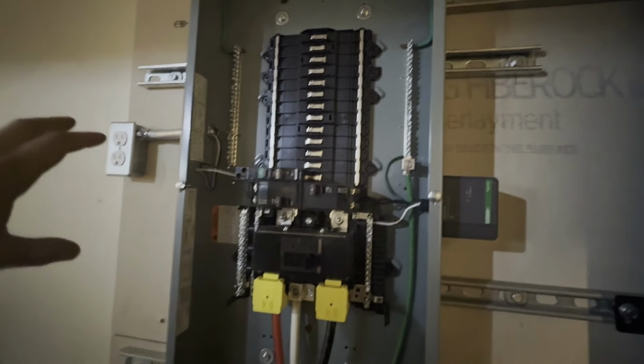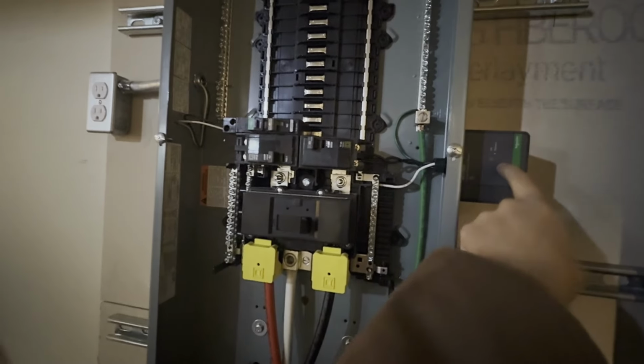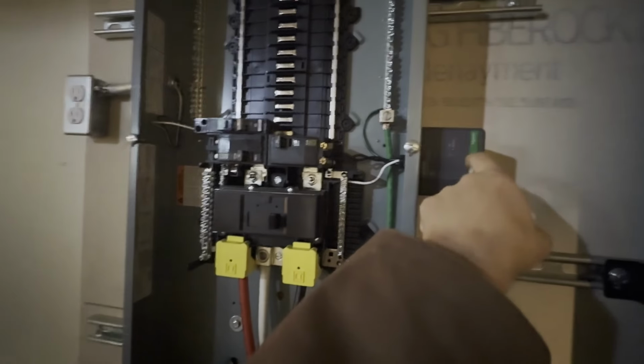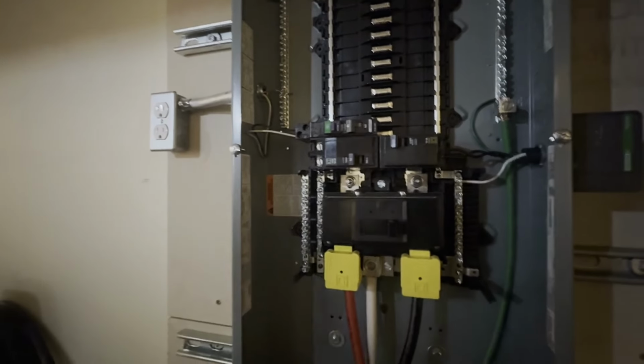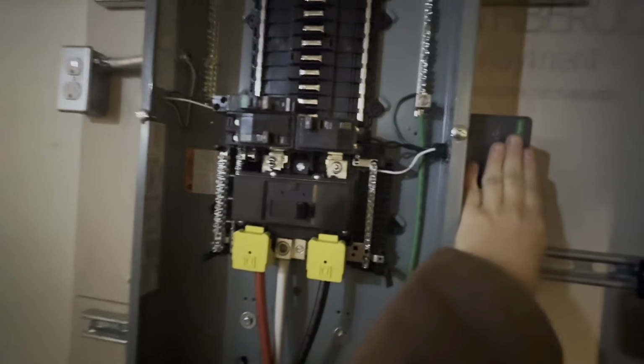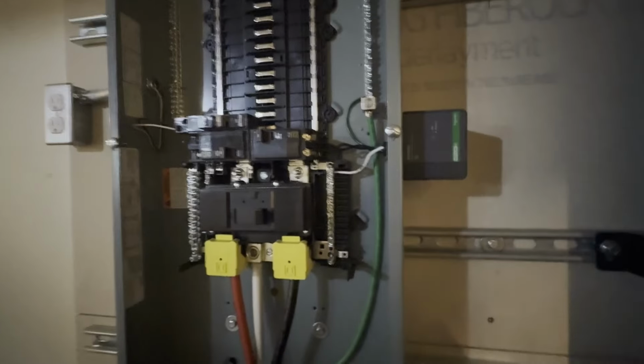It's going to come in and start traveling down all the wires equally until it gets to the surge suppressor, which will then send it to ground. So if the distance to the surge suppressor is shorter than the distance to something you care about, this will mostly protect it.